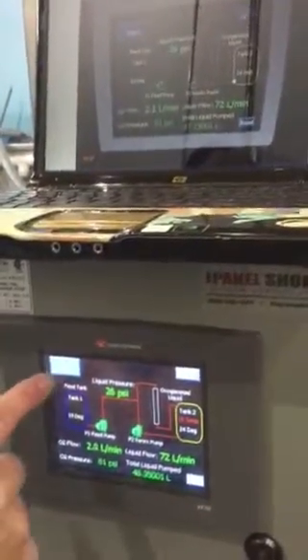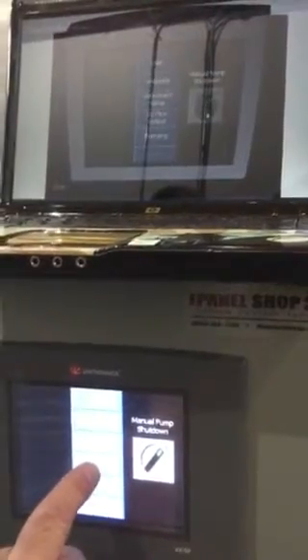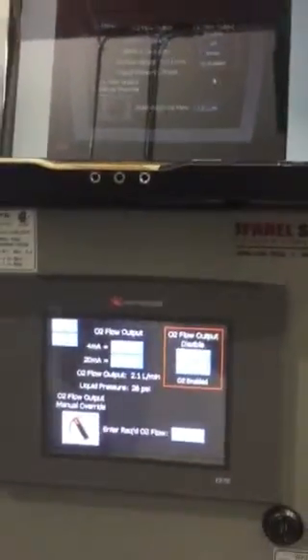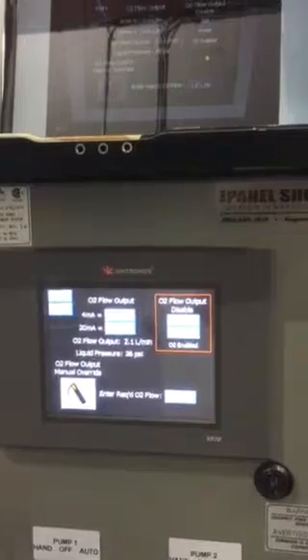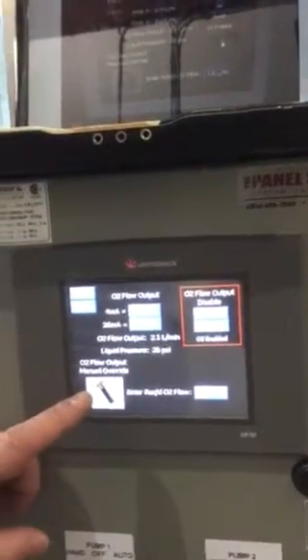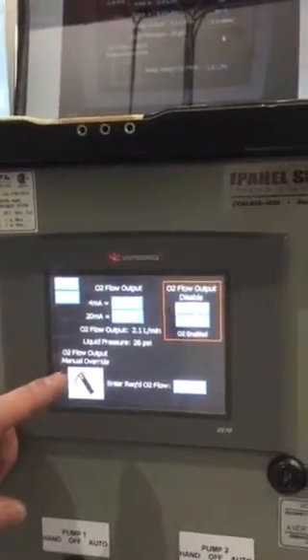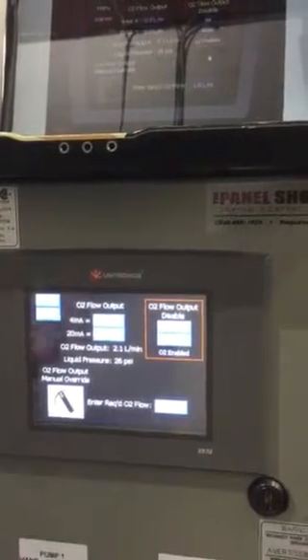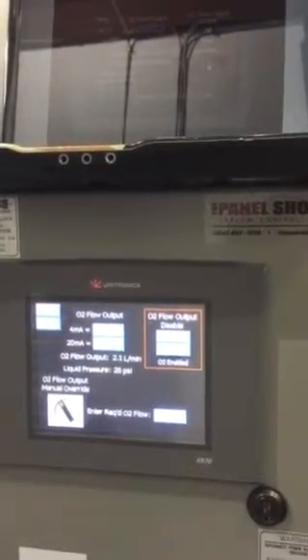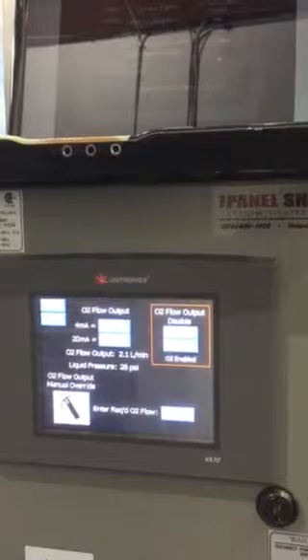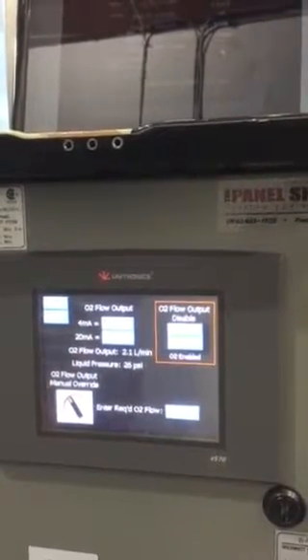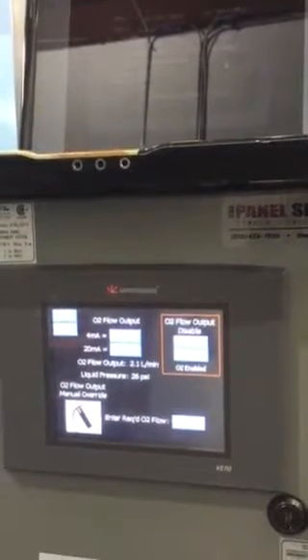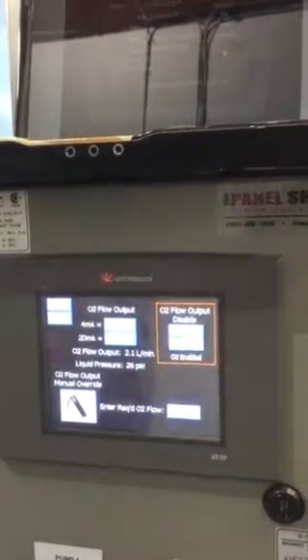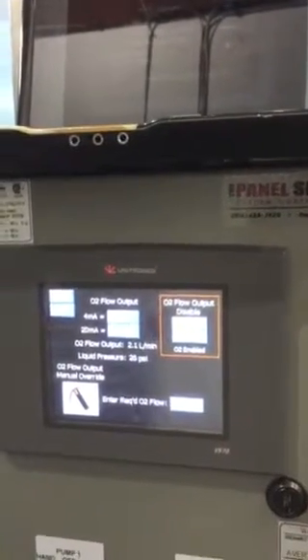Next screen. If we go down to oxygen flow output, what this does is there's a manual override. Right now it automatically follows the flow of water for the amount of oxygen that goes into the unit. So if you've got more pressure, it's going to automatically compensate by putting in more oxygen flow. So right now I'll just vary the pressure.